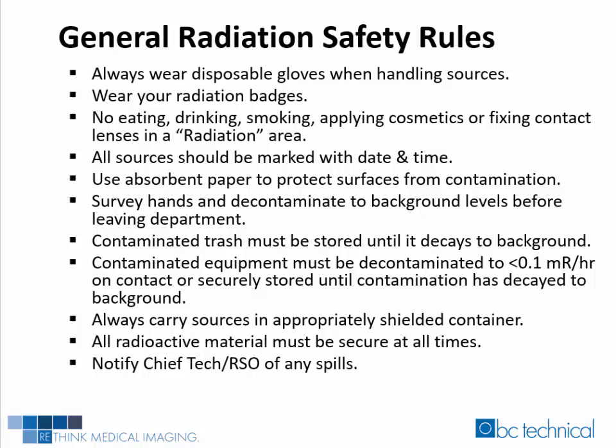Survey these areas daily and change the absorbent paper regularly. Survey hands and decontaminate them to background levels before leaving the department. Contaminated trash must be stored 10 half-lives until it decays to background. Contaminated trash should be labeled, at the minimum, with the date, isotope, and initial reading. Contaminated trash should be stored behind lead or in a designated long-term radioactive storage area, depending on the isotope being stored. Contaminated equipment must be decontaminated to less than 0.1 millirem per hour on contact, or securely stored until contamination has decayed to background. This includes treadmills. If the treadmill is unable to be properly cleaned, the contaminated areas should be covered in lead and the treadmill not used until it has decayed to background.